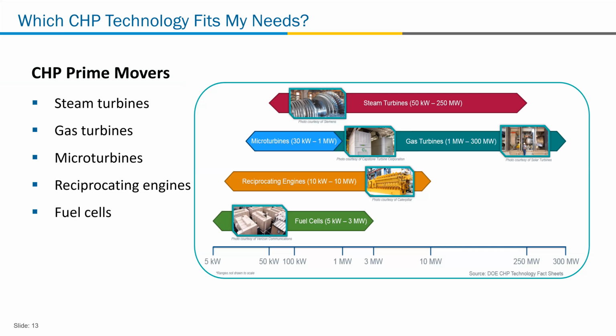From a prime mover standpoint, going back to topping cycle systems and bottoming cycles, you have steam turbines, which can run from the 50 kilowatts up to 250 megawatts. You have combustion turbines, which in the micro turbine size run from 30 kilowatts to 1 megawatt, and combustion turbines typically run from 1 megawatt up to 300 megawatts. Reciprocating engines can be as small as 1 kilowatt in CHP up to about 10 megawatts, and fuel cells generally range from 5 kilowatts to 3 megawatts. That gives you some idea of the power generation capabilities deployed in CHP systems.